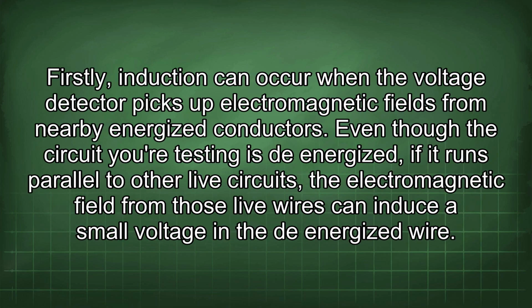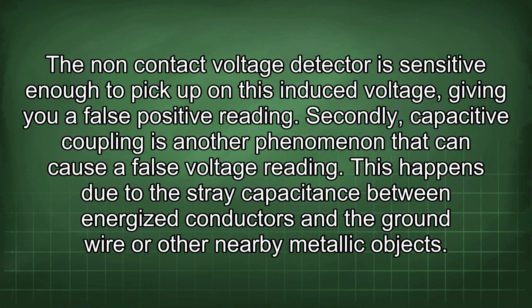Firstly, induction can occur when the voltage detector picks up electromagnetic fields from nearby energized conductors. Even though the circuit you're testing is de-energized, if it runs parallel to other live circuits, the electromagnetic field from those live wires can induce a small voltage in the de-energized wire. The non-contact voltage detector is sensitive enough to pick up on this induced voltage, giving you a false positive reading.